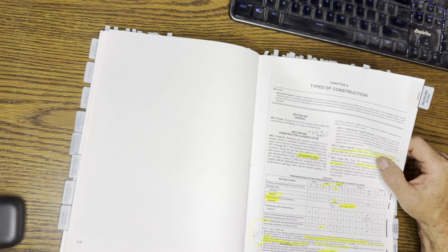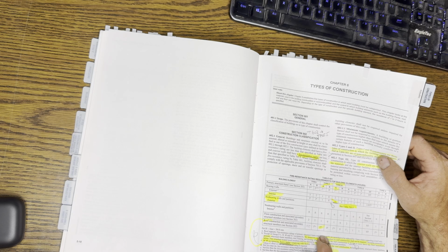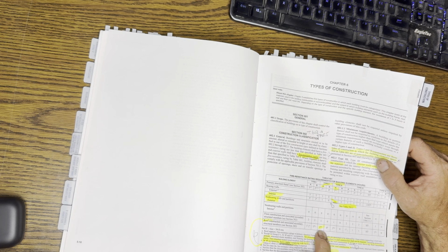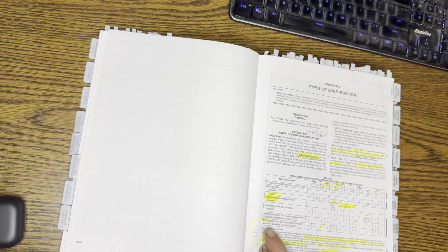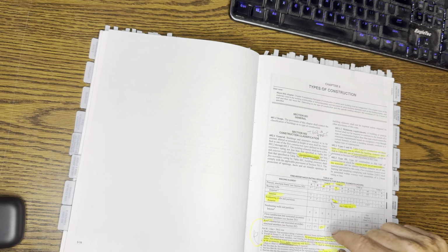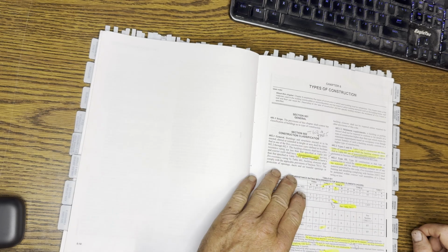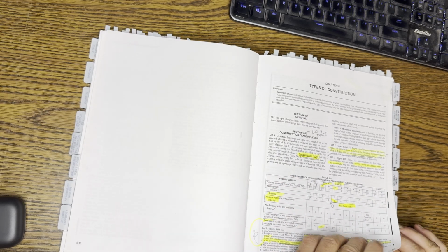Heavy timber. Yeah, so here's a question. What was it? Roofs. So type 2. Type 2 is non-combustible construction, okay? But non-combustible construction is not strict. Let's take a look. I have footnotes B and C. The question was, in a roof, can I use wood? And look, it's right there. Heavy timber shall be allowed for roof construction in a non-combustible building. So there are a few allowances like that you can use. There are a couple different ones as well.